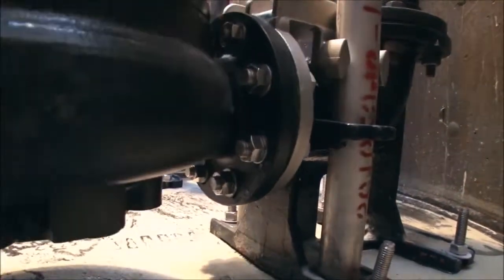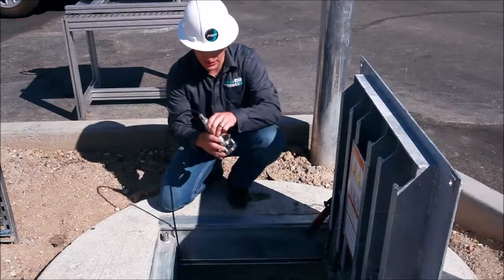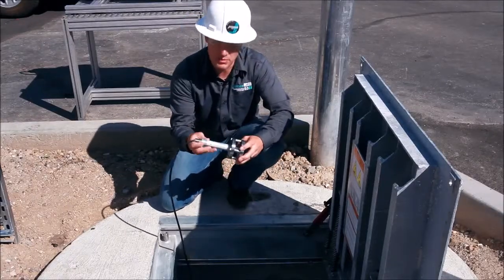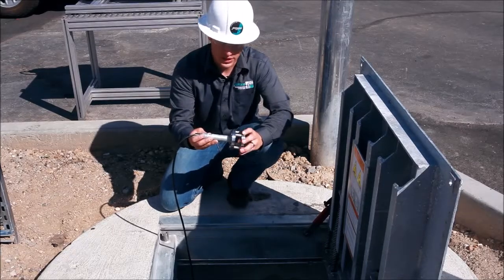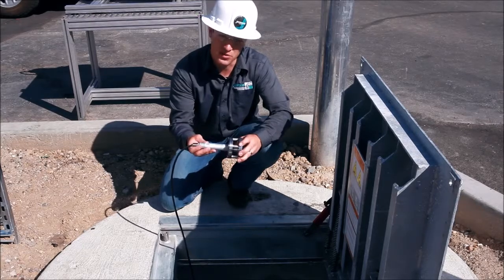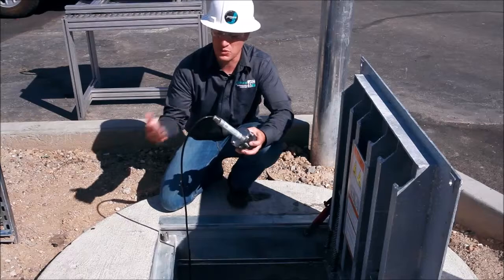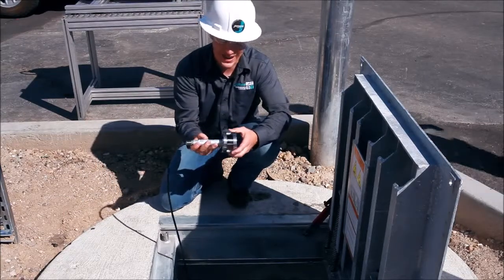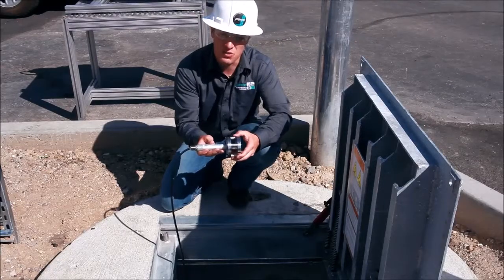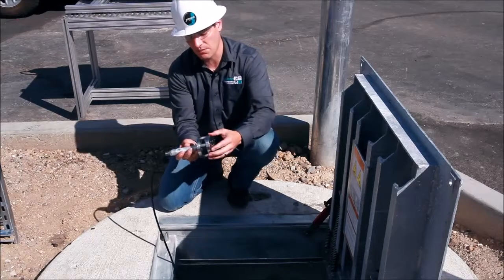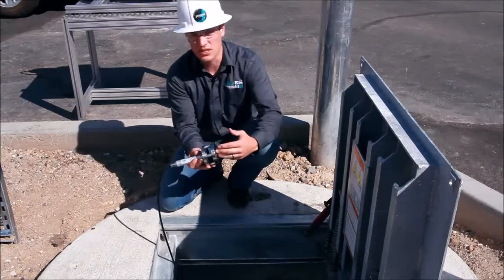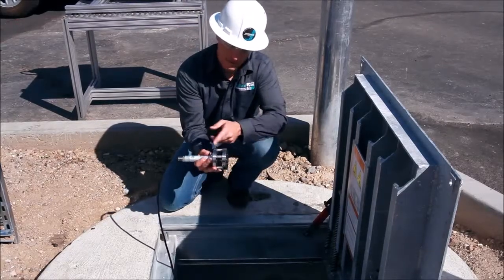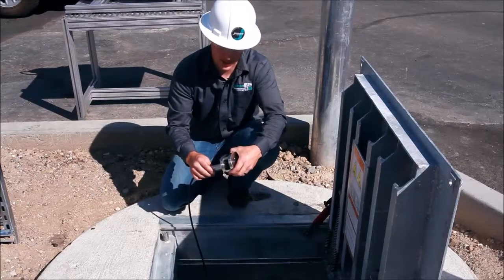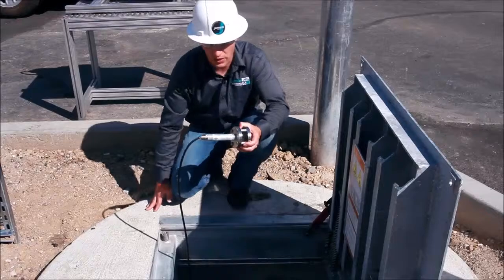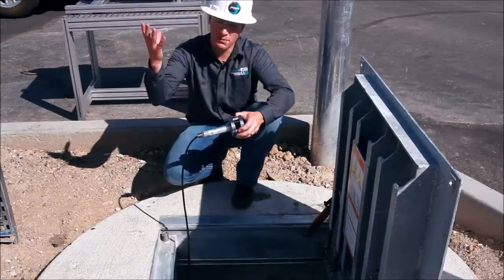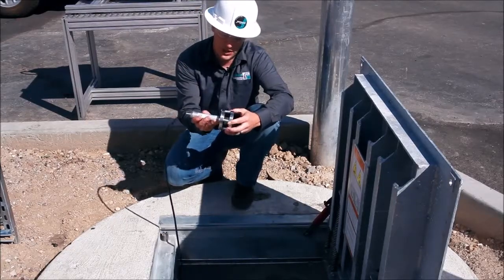For level detection on this pump station, we're utilizing as our primary level detection device a Dwyer Mercoid PBLTX pressure transducer. This pressure transducer is rated to 10 psi, which is 23 feet of head, so it can detect a water column anywhere between 0 to 23 feet. Now this specific pressure transducer is rated for sewage applications. So what that means is that we got this nice big thick bird cage, and actually the lower half of this pressure transducer is not doing anything for the level detection device. The diaphragm, which you see right in here, is the primary detection device. So the water's pushing against the diaphragm and sending a signal to our control panel. It's detecting a differential pressure between the atmospheric pressure and the pressure it's feeling from the water surface. So that's our primary level detection device.